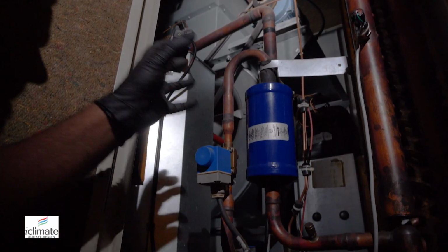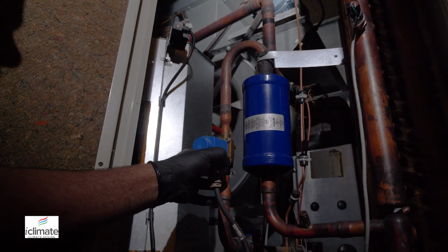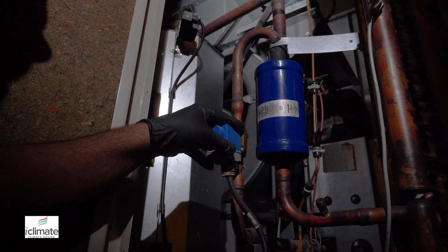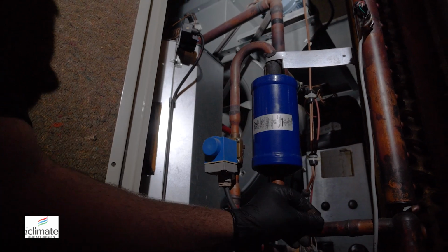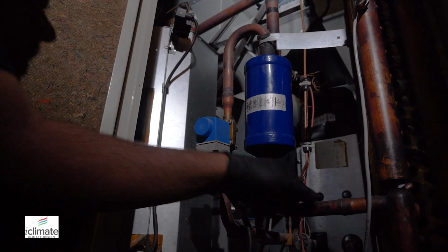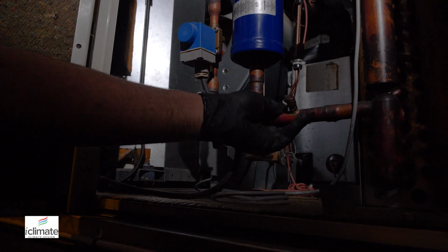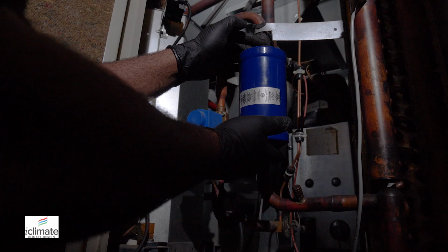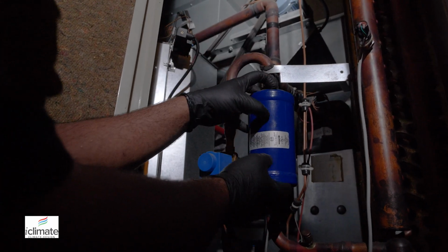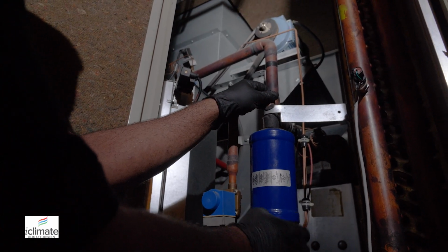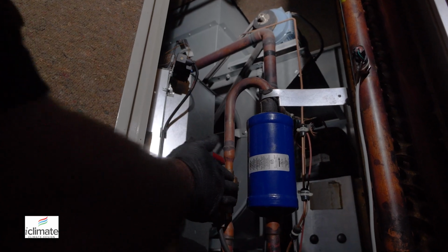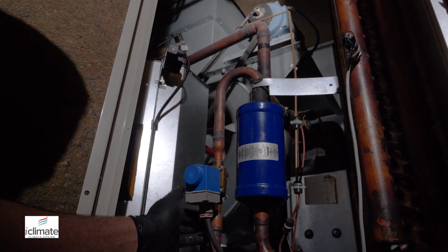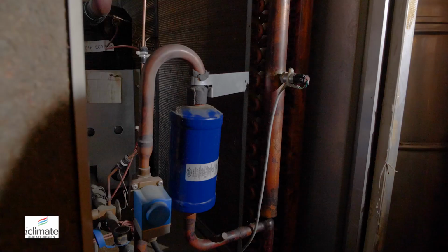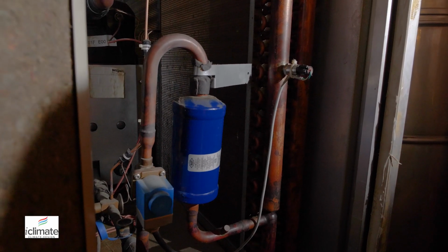So chillers are essentially a very large extrapolated refrigeration circuit. The fridge guys will know that's your solenoid valve, liquid line, that's a dryer from the condenser. We've got gauge taps all over the chiller, because when you troubleshoot a chiller, you essentially have to look at things in a local scenario. So if you had a liquid line dryer issue, you would check the delta T across the liquid line. If you had slight condensation forming, or if the solenoid valve wasn't lifting properly, you'd have some type of disturbance in the liquid line. You've got a sight glass here, which all the refrigeration guys know about, which is essentially our viewing glass as far as refrigeration guys are concerned.